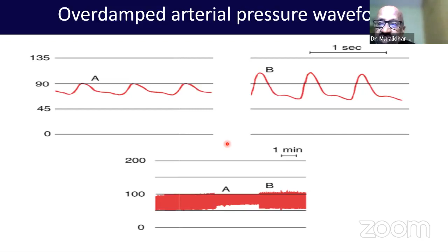The measurement of natural frequency and damping coefficient can be done bedside by using the flush test. That is, you pull the tab and release it. When you do that, the pressure suddenly rises to about 300 millimeters. That is the pressure you have exerted onto the saline bag by using a pressure bag. And then once you release it, the oscillations are produced in the arterial line system, which settle down and you get the arterial tracing just after that.